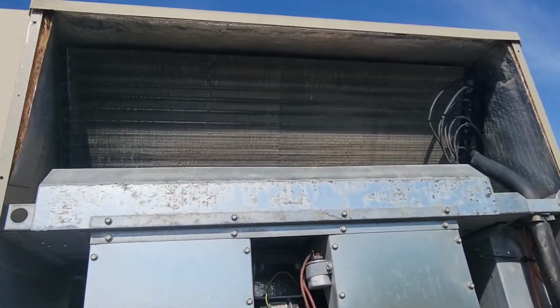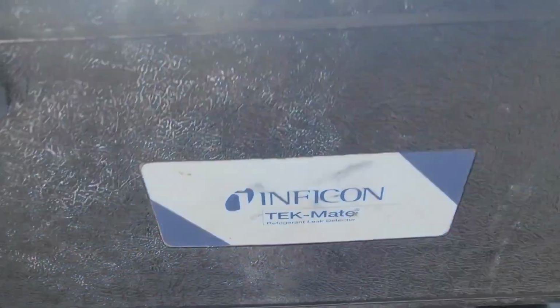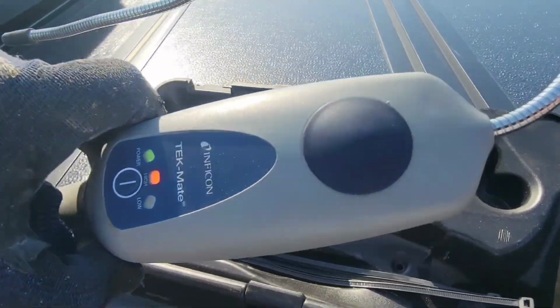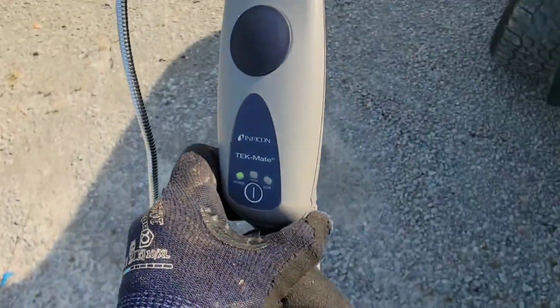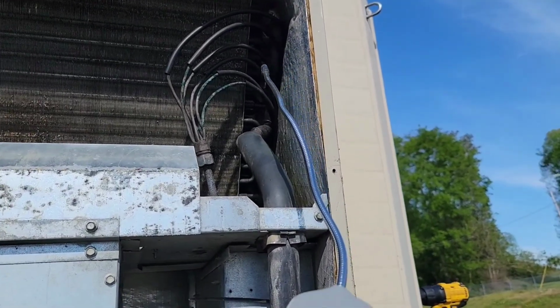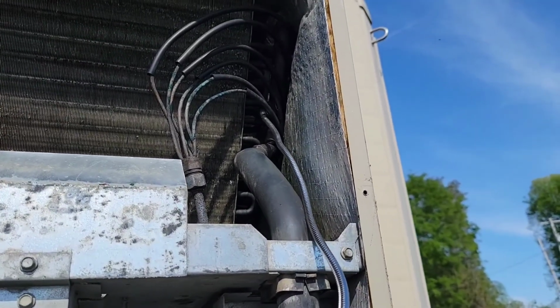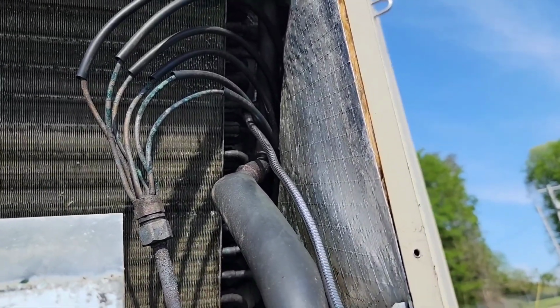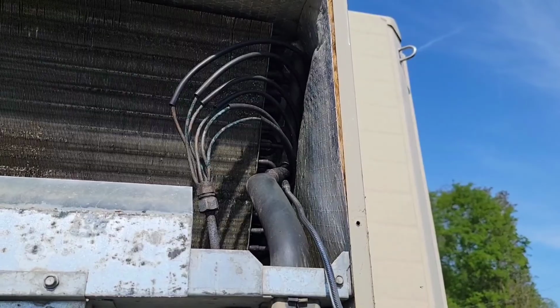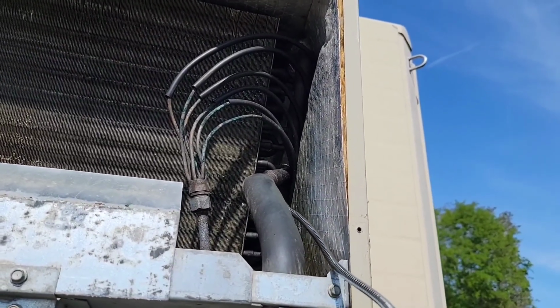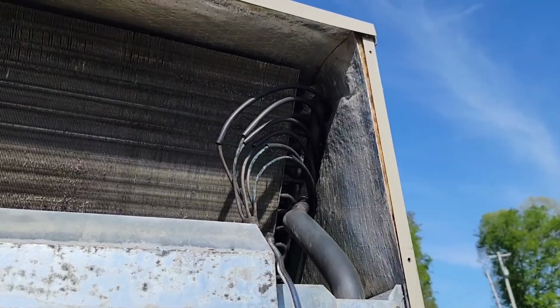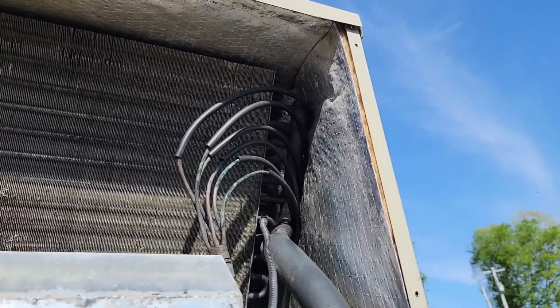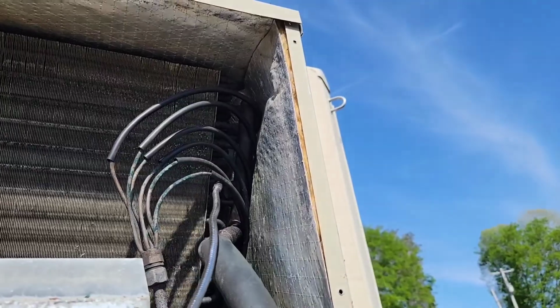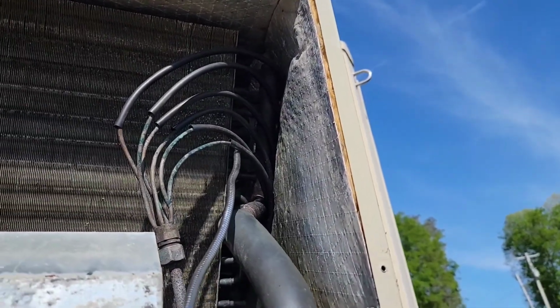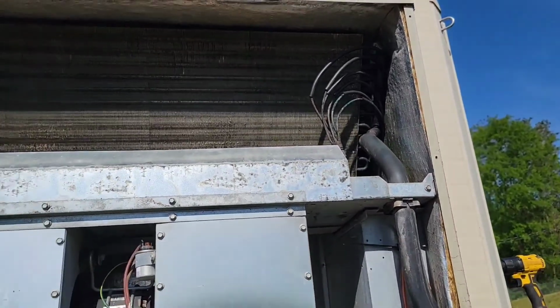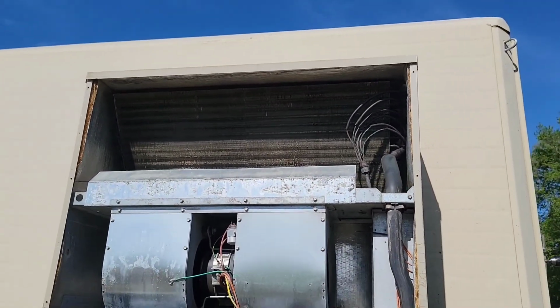All right, I'm gonna get my leak detector first. All right, wind's blowing pretty heavy. I'm gonna check the indoor coil first. That's usually where you find the leaks. In the same spots. Yep. We got a leaking indoor coil.